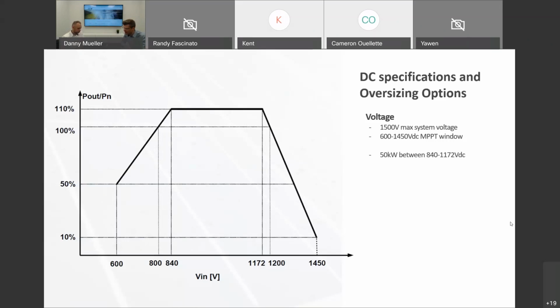The input voltage is fairly wide for such a high power 600 volt AC device because the inverter, as I said, with the boost converter and the MPP tracker in the unit, is a dual stage inverter. That means the input will first go to a boost converter, then it goes to the DC link in the inverter, and then the final inversion stage, the actual DC to AC inversion, happens in a secondary stage. Versus some other commercial products that are designed as single stage systems, where you typically have a much more narrow operation voltage window for your string sizing.